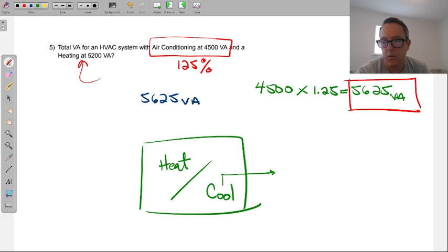Right, so here we have the cooling system at 4,500 VA, and then the heating system at 5,200 VA. So let's say someone went with the lower number, that's when you're going to start seeing your breaker trip. Exactly. If you went with the lower number, and then the heater kicks on, now you're dealing with more amperage, and your breakers could trip. Is that because you didn't calculate your demand factor correctly? That's because you didn't increase your load. Yes, it is still a demand factor, but it's an increased demand factor, not a reducing one. This one actually increases the number. So you should have done this first with the air conditioner. If now the air conditioner becomes the bigger one of the two, then we still go with the bigger one of the two. Always at the end, the bigger one of the two.